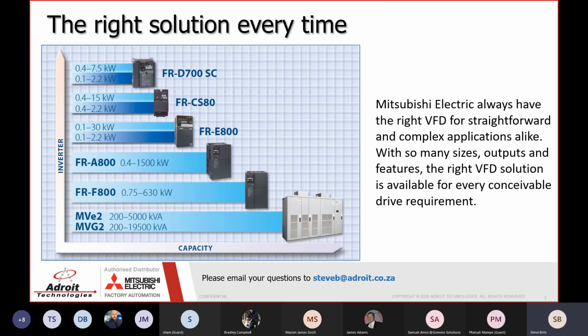So, just a quick run through the Mitsubishi Electric VFD range. We have quite a big variety of these VFDs to cover almost every last possible application that you can think of. If we start at the very small ones, that will be our D700 range, which is 0.4 to 7.5 kilowatt on the 380 volt units and 0.1 to 2.2 kilowatt on the 220 single phase unit. Then we move over to the CS80 range, which has 0.4 kilowatt to 15 kilowatt on the 380 volt range and 0.4 to 2.2 kilowatt on the 220 volt input range.